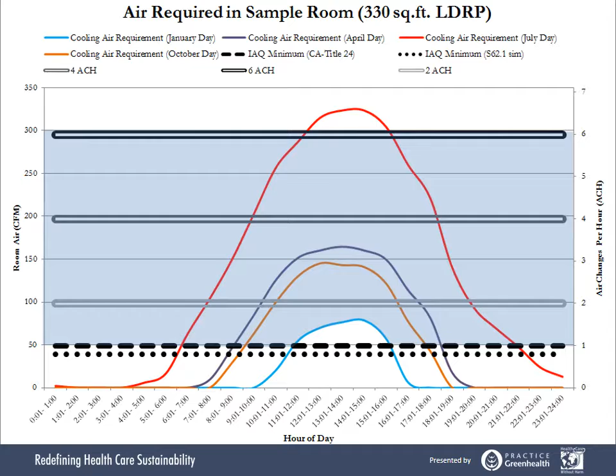Here's the amount of over-ventilation we do on a summer day in Los Angeles, and here's the amount on a winter day. All the air that gets put in this room goes through a central system. It gets moved by a fan, cooled, and reheated at the end. So if you multiply this kind of over-ventilation times every patient room in the building, or every patient room in the country, you can see why hospital energy usage is so high.